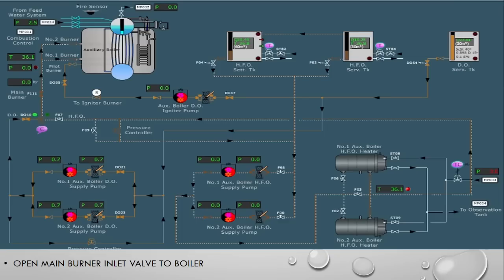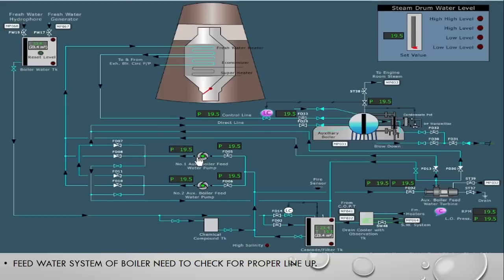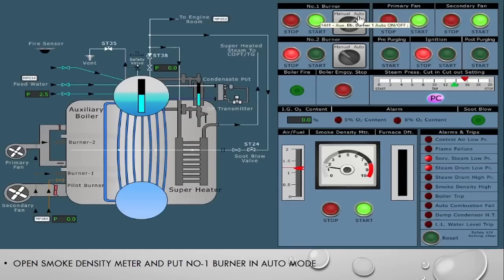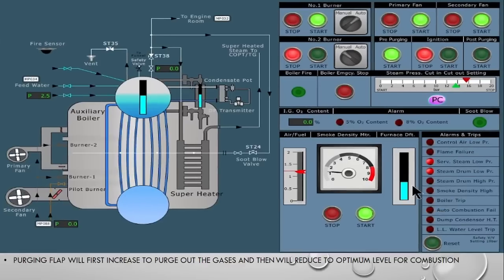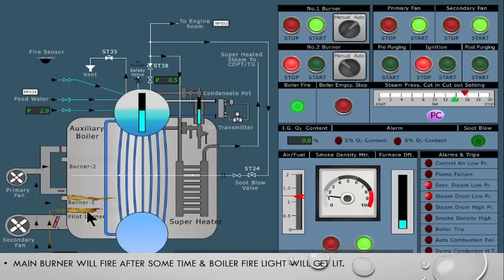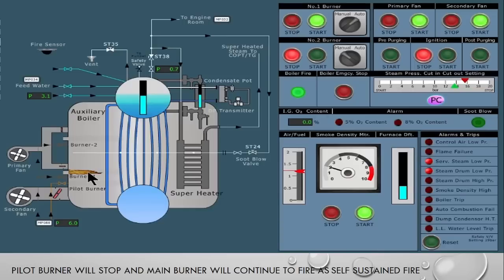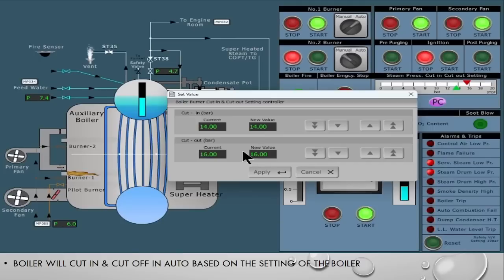So what have we learned? To summarize: after lining up the DO igniter pump and the DO supply pump, we check that the feed system lineup is proper. Then the pilot burner fires first, followed by the main burner which is initially assisted by the pilot burner. The pilot burner goes off once the main burner flame is self-sustainable. The main burner pressurizes the boiler, and after reaching the set pressure, the boiler cuts in and cuts off depending on the control panel settings. Friends, if you have learned something from this video, please do like, share, and don't forget to subscribe.